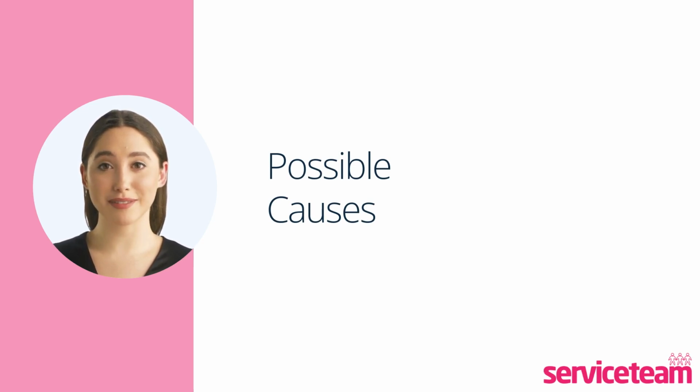1. Gas valve unit issue. A faulty or worn-out gas valve unit disrupts gas flow into the boiler, triggering the error code. 2. Gas valve leak. A gas valve leak leads to a pressure drop, resulting in the F0238 code. Remember, gas leaks are safety hazards and require immediate attention. 3. Incorrect control box. Problems with the control box communication can prevent proper operation and trigger the error code.